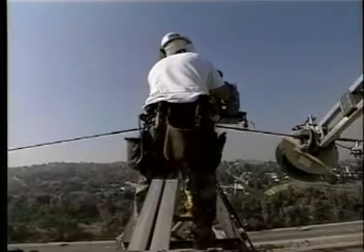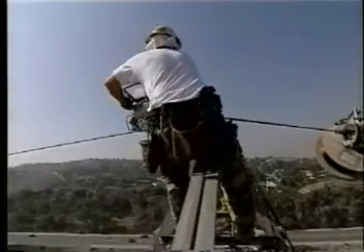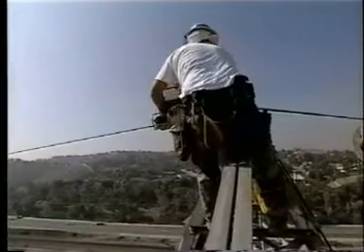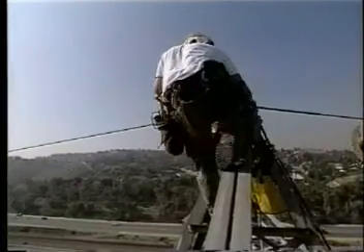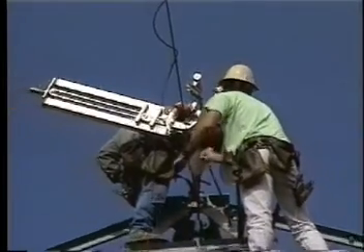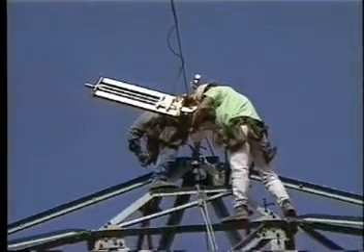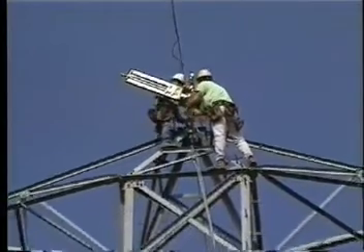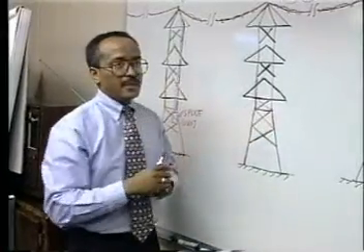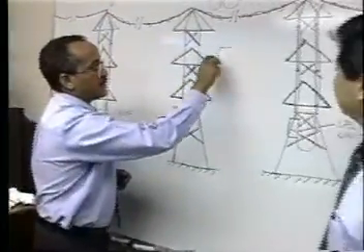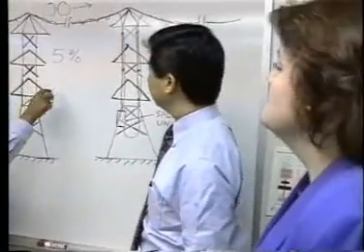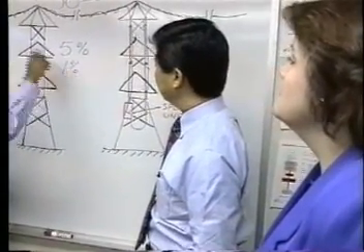When the machines reach towers along the route, a carryover is performed where the machines are carried over the tower and reattached to the conductor. If the next tower is reached when the cable reel is nearly empty, the cable is fed down the tower so a splice point can be made. When calculating which towers along the route will be used as splice points, 5% of the total cable length on the reels must be allowed for wrapping, slack cable for splicing, and cable sag.